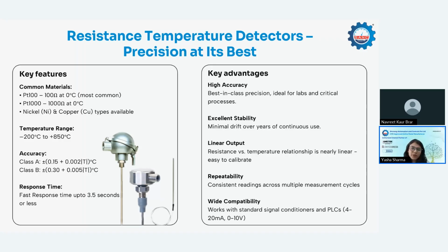Nickel and copper types are also available, but these are used for the low temperature range. When we are talking about RTDs only, platinum is for the higher temperature range. The temperature range that RTDs cover is from minus 200 degrees centigrade to plus 850 degrees centigrade.